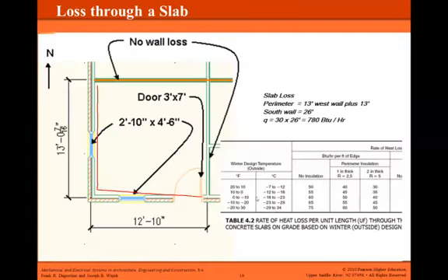So in this case, we're going to take the 1-inch insulation, we'll get the perimeter, it will be 26 feet times the F factor of 30 if we have 2 inches or R5 insulation. So this chart's basically developed for 2 R values for perimeter insulation or thickness of insulation and the outside design temperature.